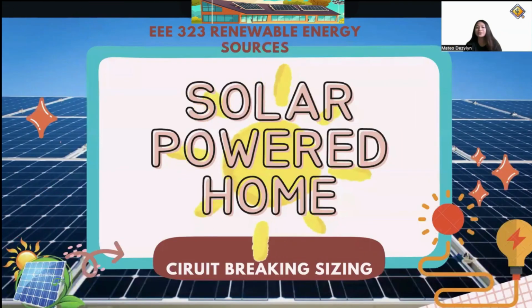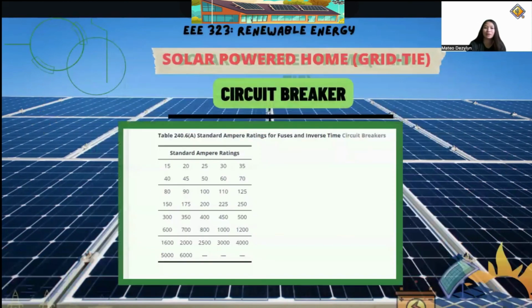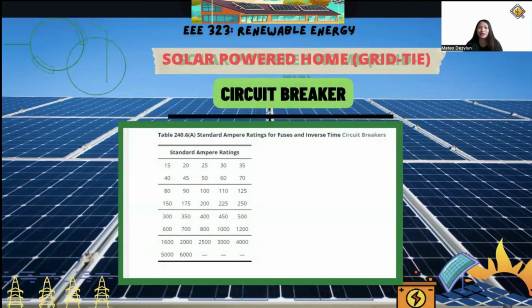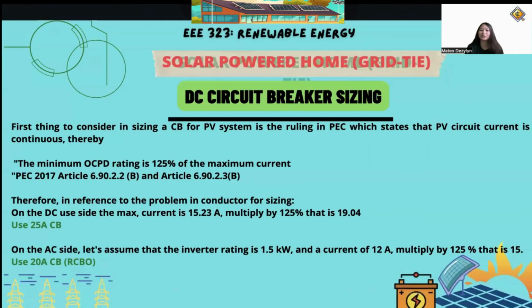Now, let's proceed to circuit breaker sizing. So, we can see here the table 240.6A, standard ampere ratings for fuses and inverse time. So, these are the examples of standard ampere ratings. Now, let's proceed to DC circuit breaker sizing.